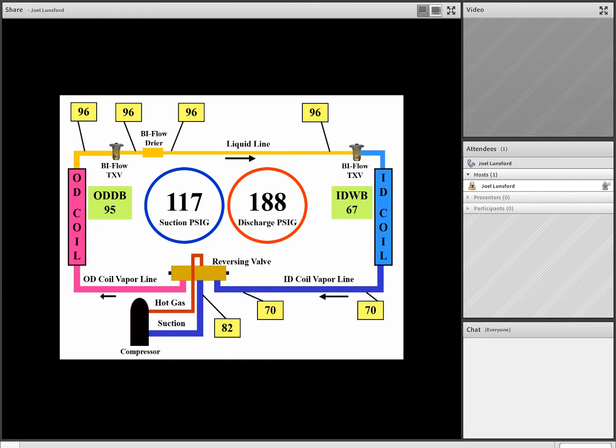Now remember, team, one of the big things that we always want to look for, whether it's an R22, R410A, or any system, is when we take a look at the reversing valve, if we've got high suction pressure and low discharge or liquid pressure, which we have in this case here, our pressures are way out of whack. And so at 117 pounds of suction pressure, which is very high for an R22 system, and 188 pounds of discharge pressure, which is actually low for an R22 system, the first thing that we always want to check is the temperature across the reversing valve, the two cool lines of the reversing valve.